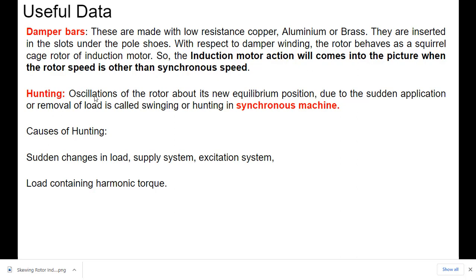Hunting. Hunting means oscillations of the rotor about its equilibrium position due to the sudden application or removal of the load. And this is called as hunting and this occurs in synchronous machine. So here, if removal of the load takes place, rotor speed increases. Rotor speed increases means it will act as an induction generator.